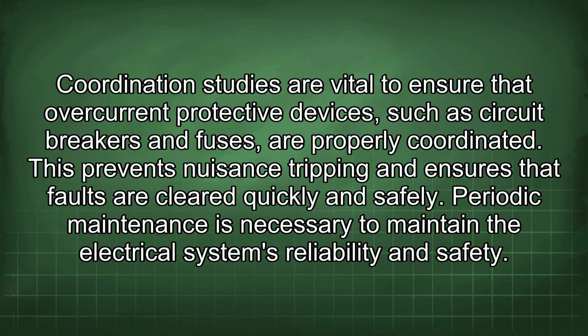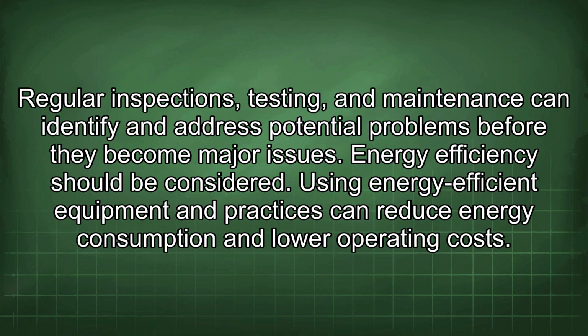Coordination studies are vital to ensure that overcurrent protective devices, such as circuit breakers and fuses, are properly coordinated. This prevents nuisance tripping and ensures that faults are cleared quickly and safely. Periodic maintenance is necessary to maintain the electrical system's reliability and safety. Regular inspections, testing, and maintenance can identify and address potential problems before they become major issues.